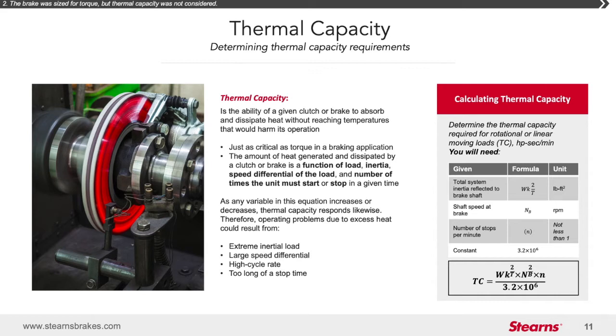To calculate thermal capacity, it is the total inertia reflected to the motor shaft at the brake times the shaft speed at the brake squared times the number of stops per minute divided by 3.2 times 10 to the sixth power. This is often overlooked where torque is considered and calculated and thermal capacity is not considered. It is important to determine whether or not the brake can handle the amount of heat generated by the energy the brake needs to stop.